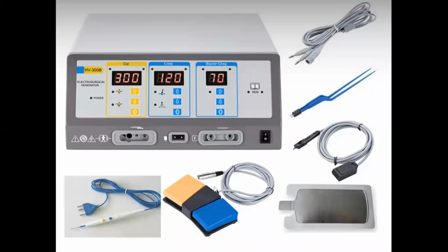Okay. Then you have your leg pedals. If you want a monopolar and you don't want to use your hand, you can just use the pedal. Then you have an earth plate, which is used with your monopolar, and cables, and this is the machine that sets your limit for coagulation. So you say monopolar, they will connect it here. This is your monopolar. You see, this thing goes into here. If you go to the OT tomorrow and have a look at it, you look at the end of the plug here, it goes here. So that's why you have cut and coagulate.